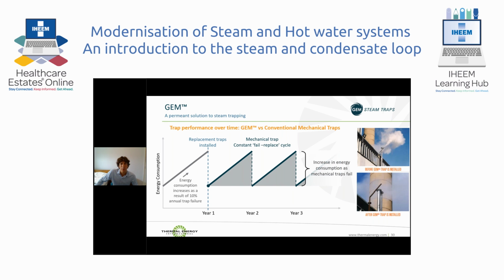The first area where the GEM traps realise energy savings is that they eliminate this steam loss through failed traps. We can also demonstrate, as I said earlier, that the GEM trap is more efficient than fully functioning mechanical steam traps, resulting in a saving. This saving is then performance guaranteed for the life of the steam trap. If you want to know where the steam goes, it's lost out the vent. This is a hospital vent before and after GEM traps were installed throughout the facility.